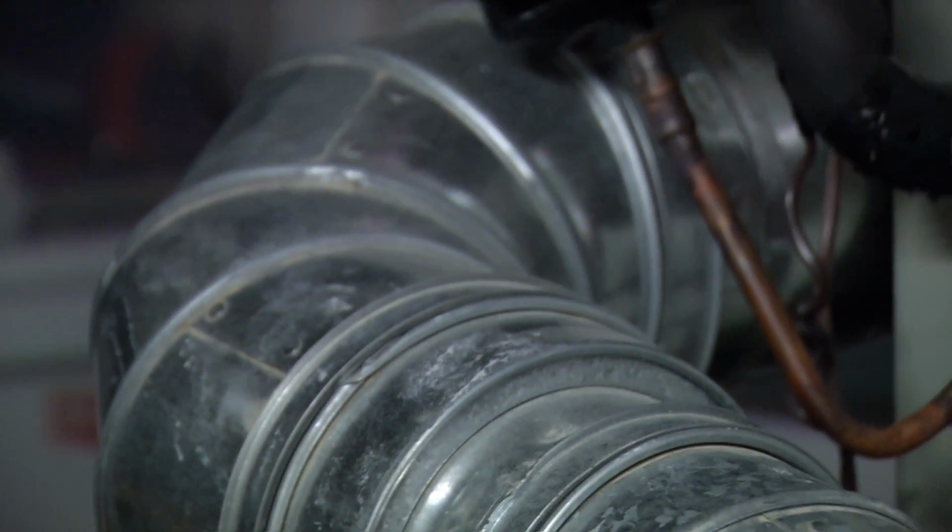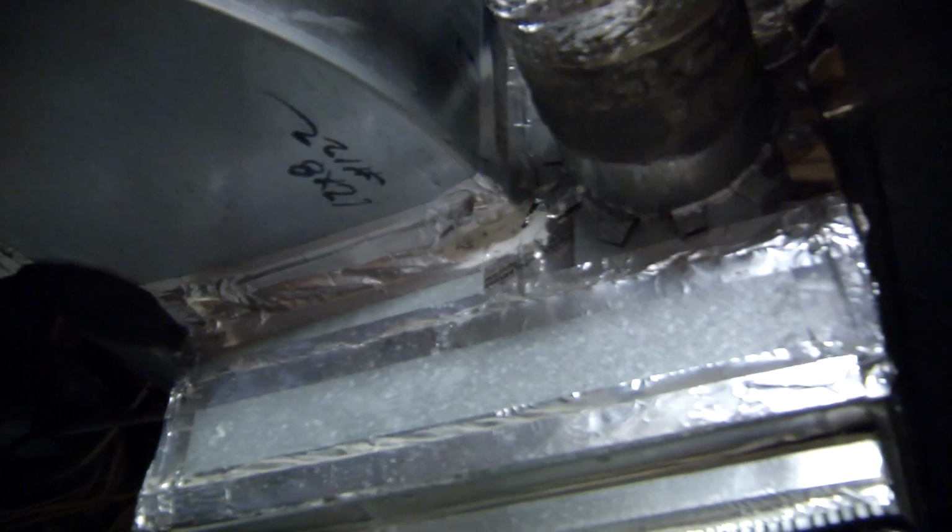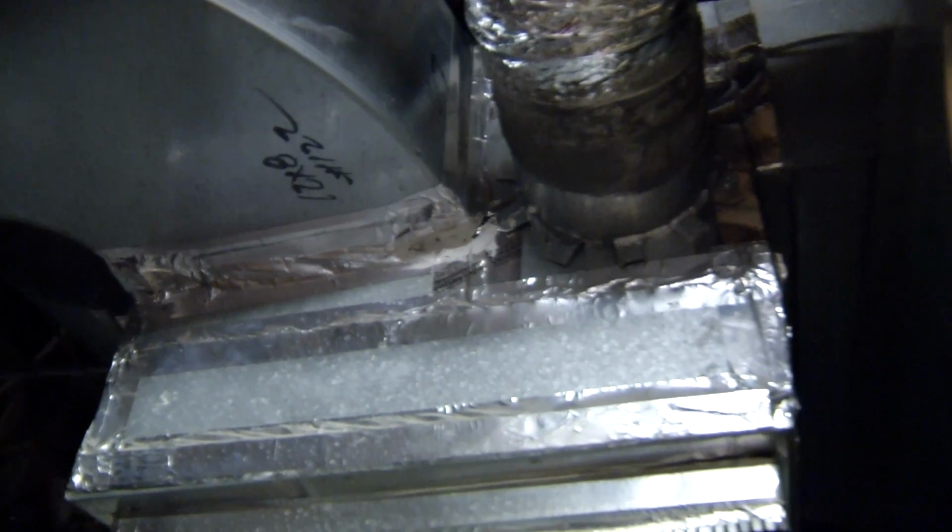Great. Sounds good. So what we're going to do is run a few tests that I like to call stress tests for your furnace and your water heater. The way they work is that we're going to make sure that they will vent the exhaust gas properly out of here.